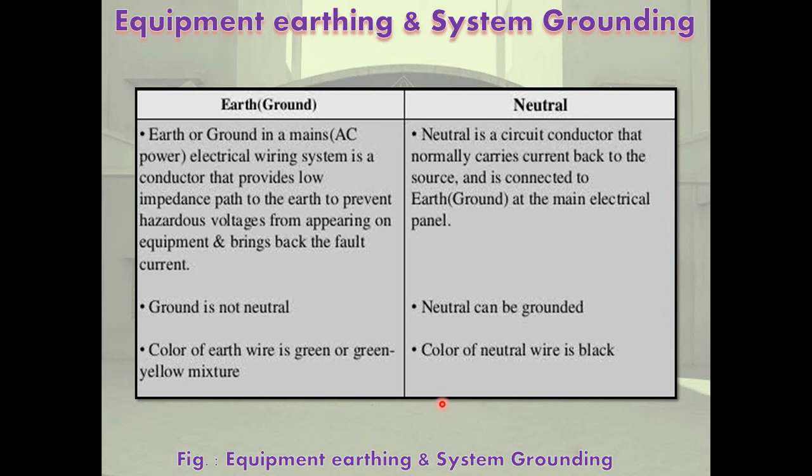Modern three-phase AC systems have gained universal acceptance due to the neutral earthing facility available. Neutral earthing is also called neutral grounding or system grounding. It has the following significant advantages. First, the neutral point remains stable in grounded systems. Without it, the phase to earth voltages of the three phases vary with time.